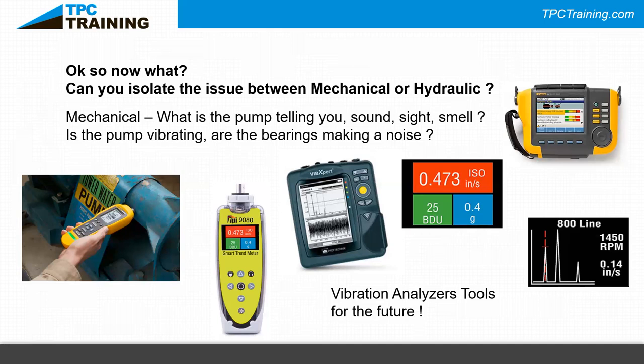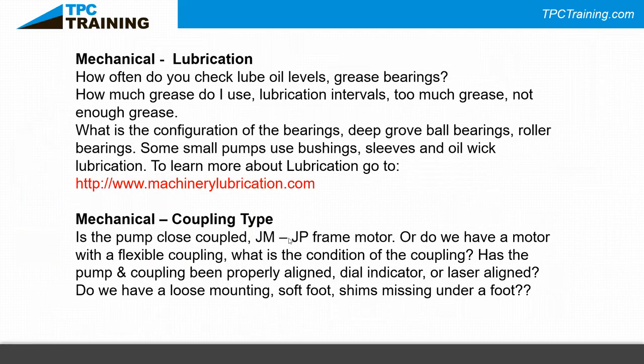The TPI meter focuses on vibration in inches per second — the ISO reading — and on bearing damage units, indicating the condition of the bearings. A maintenance person can readily identify whether the problem is vibration or bearing damage. These tools have come down significantly in cost. The vibXpert tool used to cost $25,000-$30,000; the TPI 9070/9080 now runs around $400-$600 depending on version — making them much more accessible.